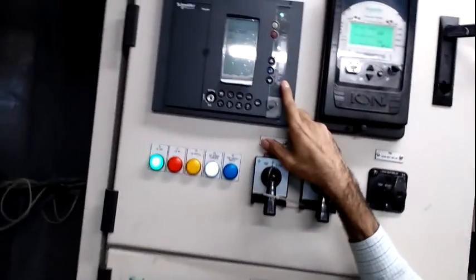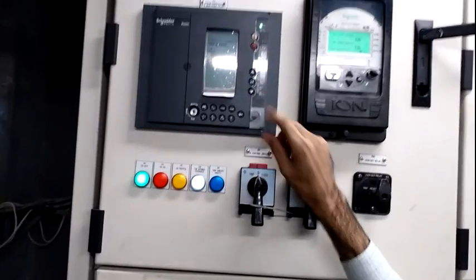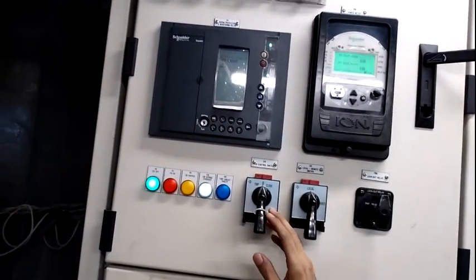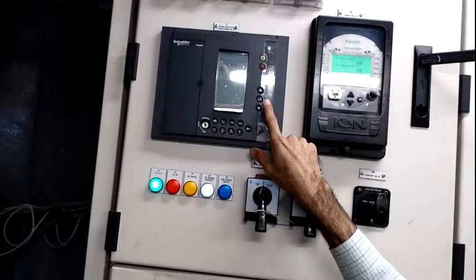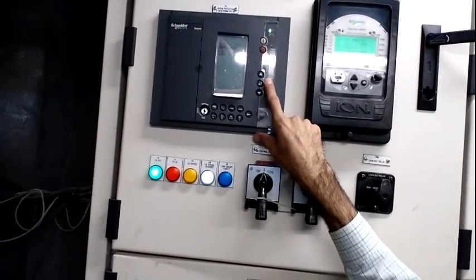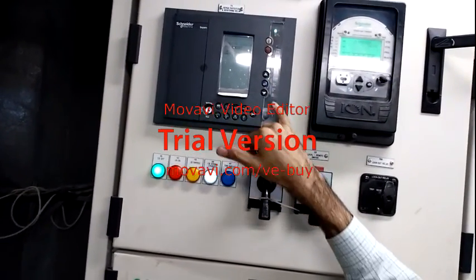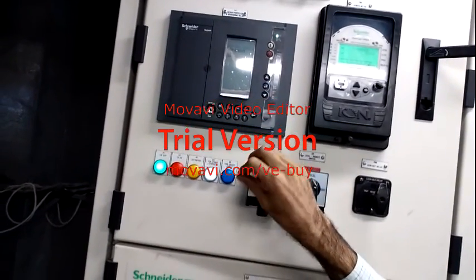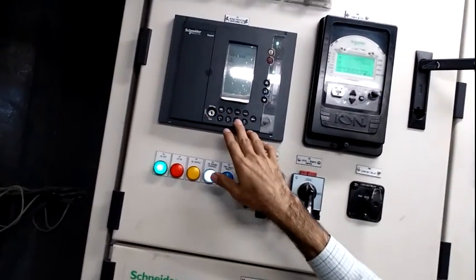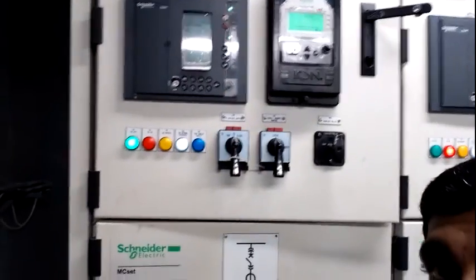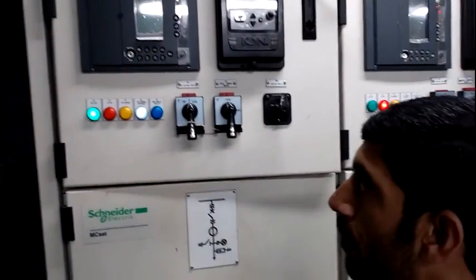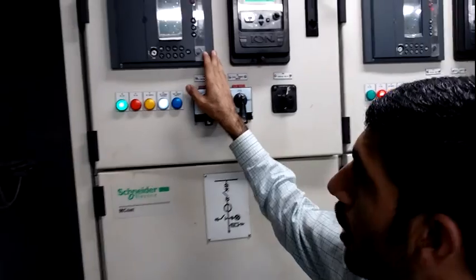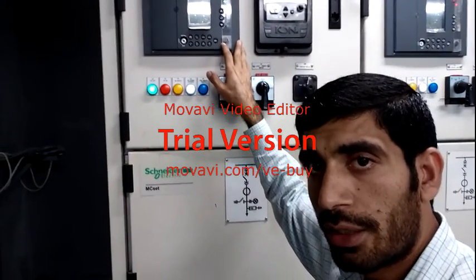If any fault happens, the indication will come. For example, for over current, the first stage indication will be on, and in the second stage this indication will be on, and likewise the earth fault first stage and second stage. If there is a short fault, this indication will be on. You can also see in this relay phase to neutral voltage, phase to phase voltage, your load, and also at which time your breaker closed and opened, or tripped for under voltage and over voltage.